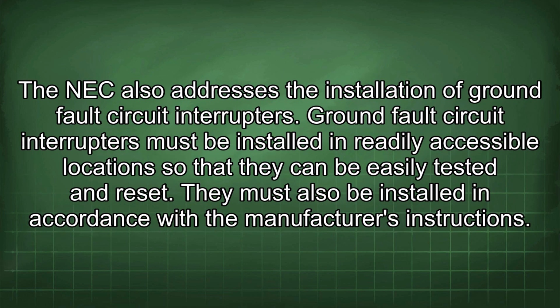The NEC also addresses the installation of ground fault circuit interrupters. Ground fault circuit interrupters must be installed in readily accessible locations so that they can be easily tested and reset. They must also be installed in accordance with the manufacturer's instructions.